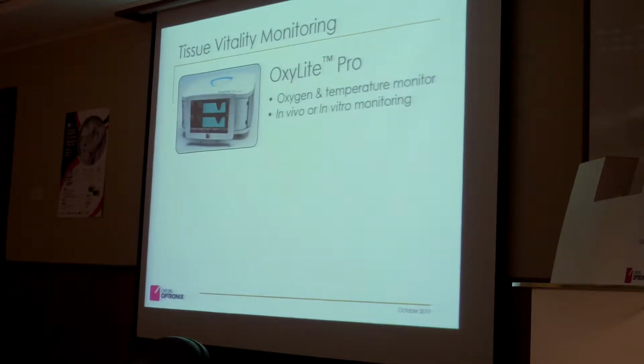So this is how the OxyLite looks. We do have a 2-channel system, which means you can connect 2 oxygen sensors combined with 2 temperature sensors. Or we have a 4-channel system where you can also measure on the other side. And this instrument is used for in vivo or also in vitro monitoring in cell culture, if you want to know what your partial oxygen pressure is in the medium in which the cells are growing.